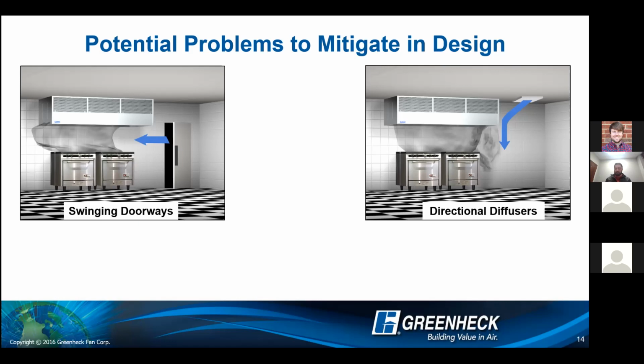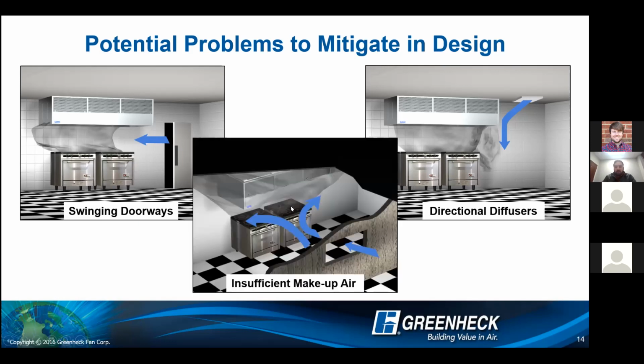Now, we know that is not always possible. We have these small kitchens that we're redesigning or just small kitchens that we're building. You have to get some outside air diffusers within 10 feet of the hood. But wherever possible, best practice design is to keep them at least 10 feet from the hood. The final potential problem to mitigate is just insufficient makeup air. If we have insufficient makeup air, eventually that exhaust fan will be starved and capture will be affected.